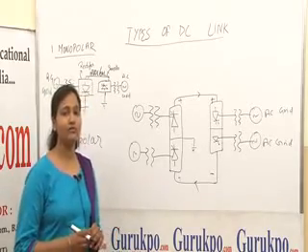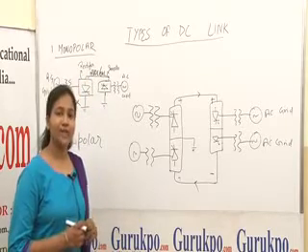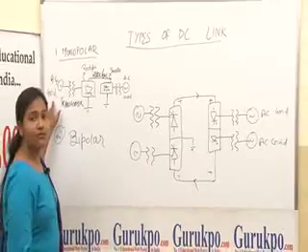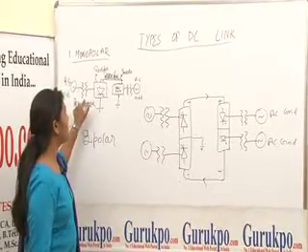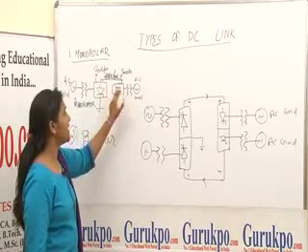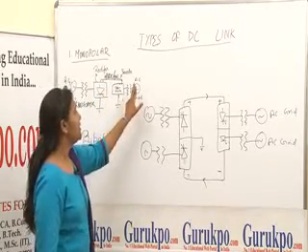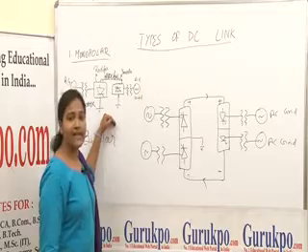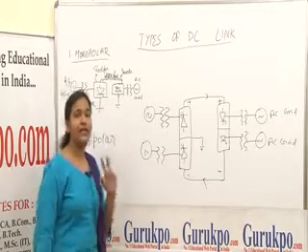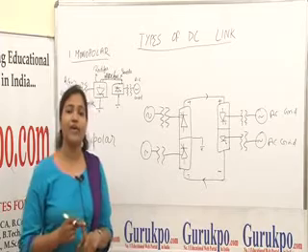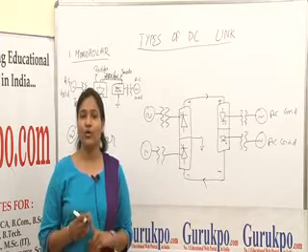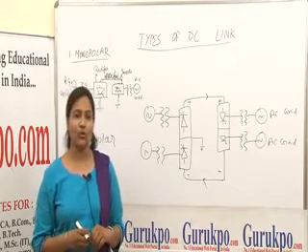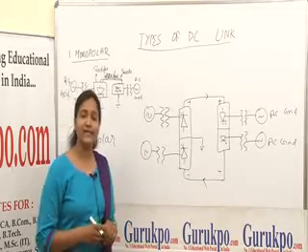First, I will discuss the monopolar type of DC link. In the monopolar type of DC link, we have an AC grid for the AC source, then a transformer, rectifier station, overhead transmission line, inverter station, transformer, and again the load side AC grid. In the monopolar DC link, ground behaves as the return path. It is basically a single conductor type of link system in which only one conductor is used, and the other conductor to complete the circuit is used as the ground. Ground path provides basically low resistance.